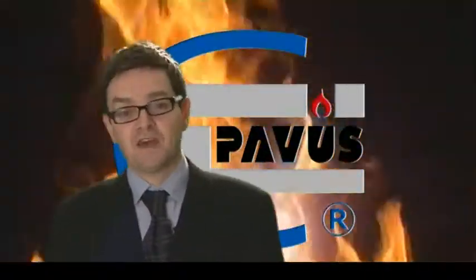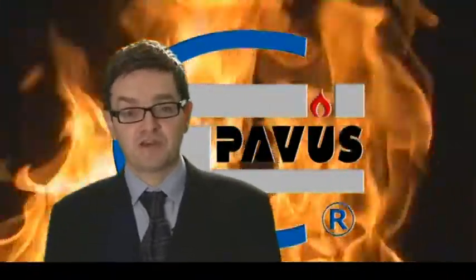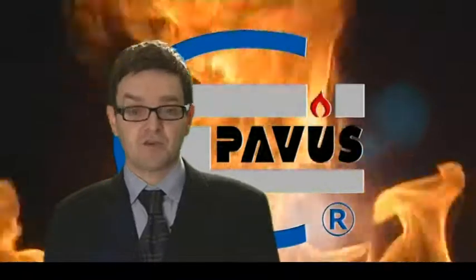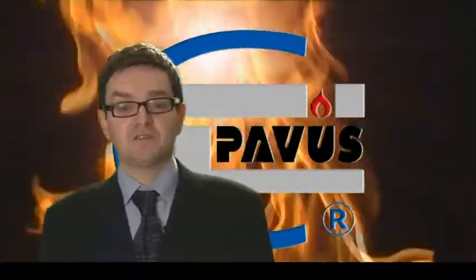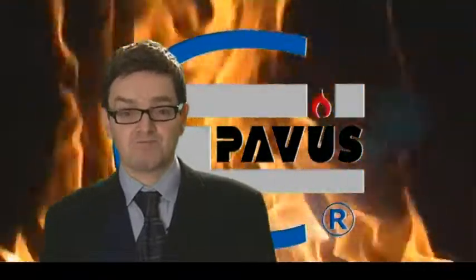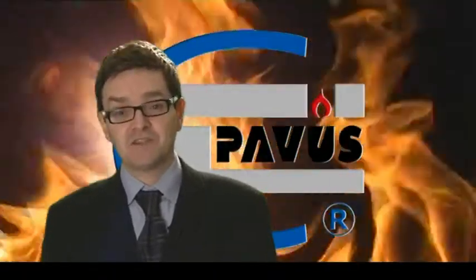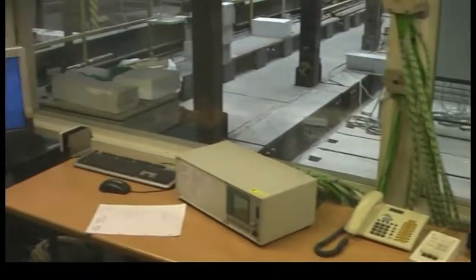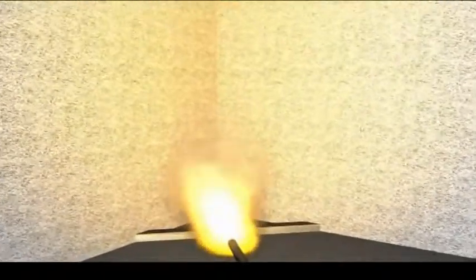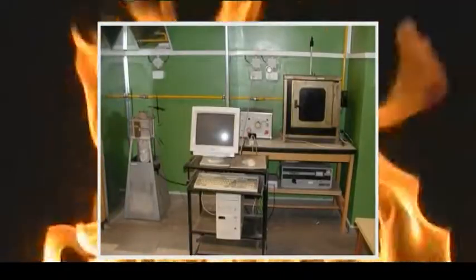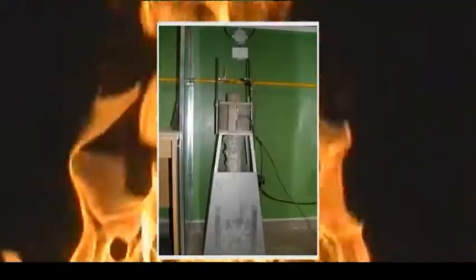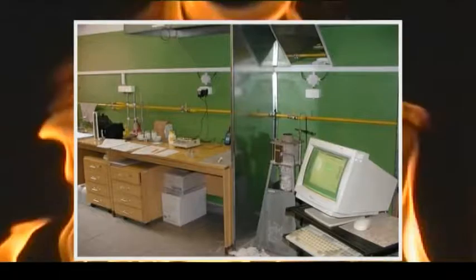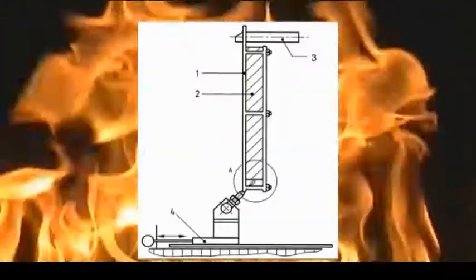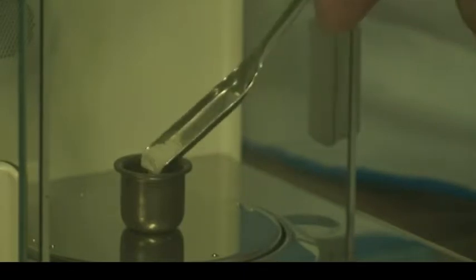Reaction to fire testing. The reaction to fire of a given product may be considered the response of the product or material to the fire to which it is exposed, contributing by its own decomposition to fire development under given conditions. Products are evaluated at end-use conditions in the building. PAVUS Fire Laboratory manages all the test methods, apparatus and equipment used for construction products' reaction to fire testing. For example, non-combustibility test, according to EN ISO 1182. Single flame source test, according to EN ISO 11925-2.